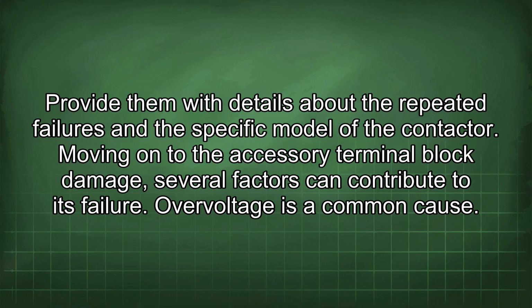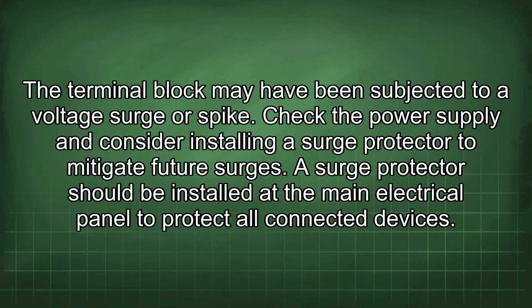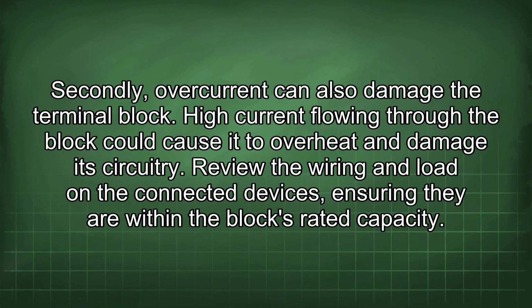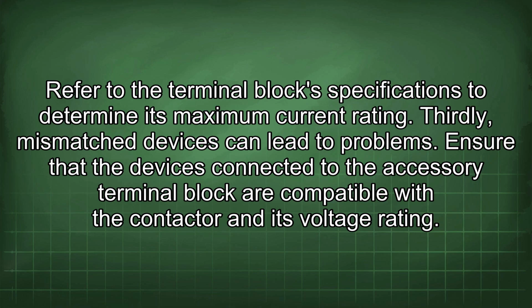Overvoltage is a common cause. The terminal block may have been subjected to a voltage surge or spike. Check the power supply and consider installing a surge protector to mitigate future surges. A surge protector should be installed at the main electrical panel to protect all connected devices. Secondly, overcurrent can also damage the terminal block. High current flowing through the block could cause it to overheat and damage its circuitry. Review the wiring and load in the connected devices, ensuring they are within the block's rated capacity. Refer to the terminal block specifications to determine its maximum current rating.